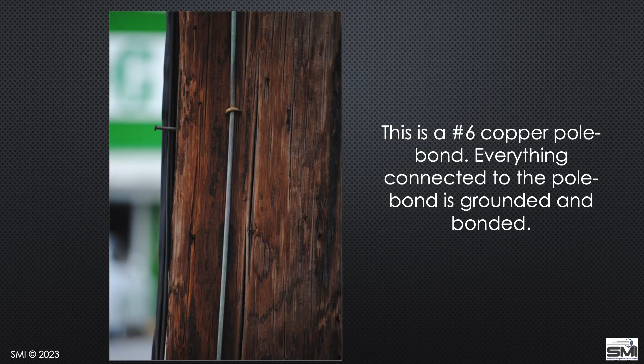The number 6 copper pole bond. Everything connected to the pole bond is grounded and bonded. So a ground wire coming down the pole, the system neutral is bonded to it. The telephone and communication cables usually bond to that too, because we need a good ground to operate our equipment. A lot of people don't realize this, though they should now that Jim has been here teaching some of the grounding platforms.